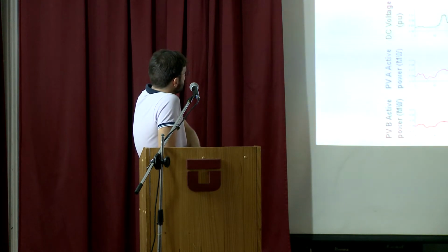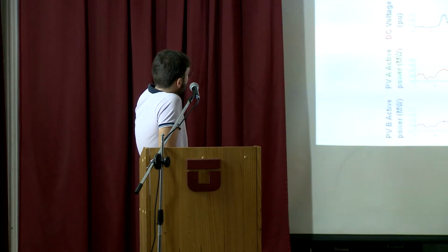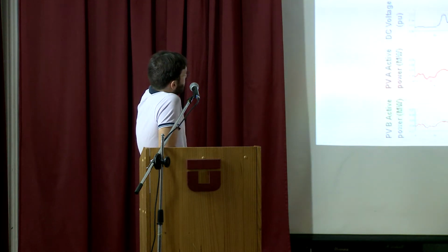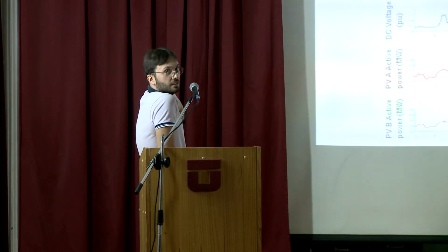So we can see that, okay, even here, this is the DC voltage that normally is at this level, and then because we are already at the edge of the reverse power flow, when the power goes up a bit, the voltage goes up, it doesn't reach the limit, but I can see that at this point, the frequency is accelerating.